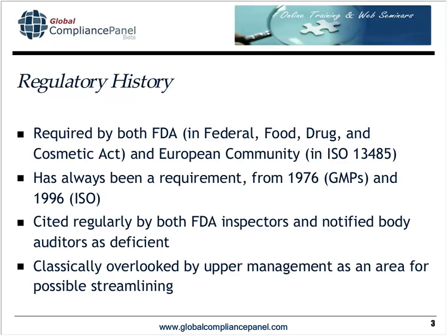Document control is regularly cited by FDA inspectors and notified body auditors as deficient, because there's so much that constitutes a document control system. You can be as attentive as possible and still have an issue fall through your hands. I recommend not spending too much time reviewing every single aspect — you will drive yourself crazy. Your goal is to make document control part of all aspects of your internal audit program, whether you audit by ISO element or FDA subsystem.